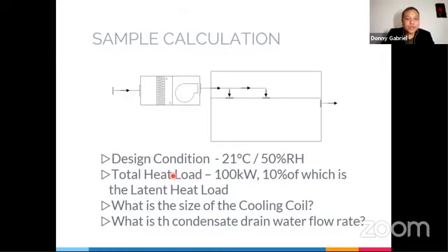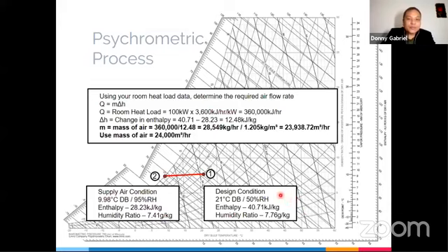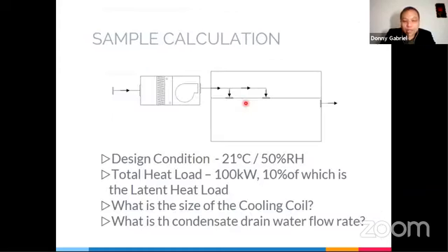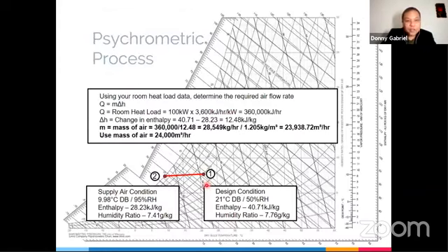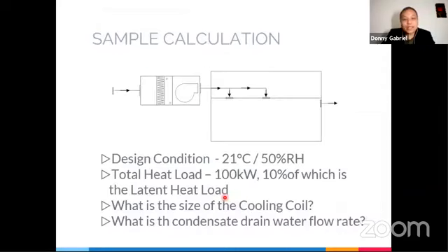Okay. So going back to our question, what is the size of the cooling coil? Using the room heat load data, we can calculate what is the required air needed to cool down the room. So this is your room setting. You know that it's 100 kilowatt for room heat load.